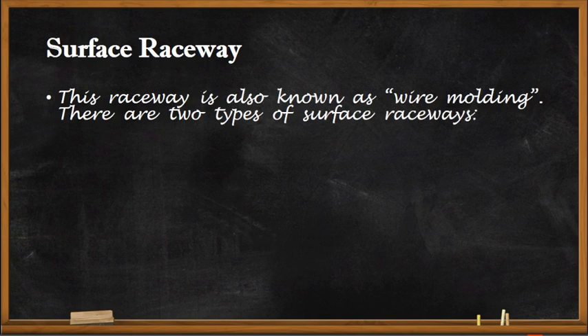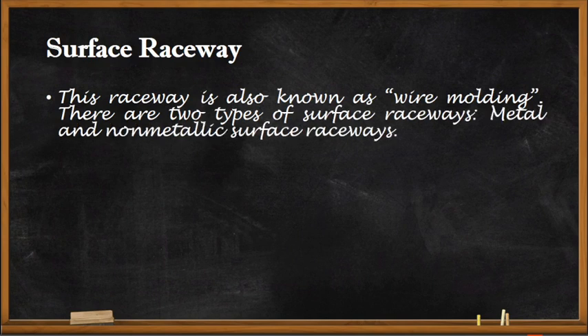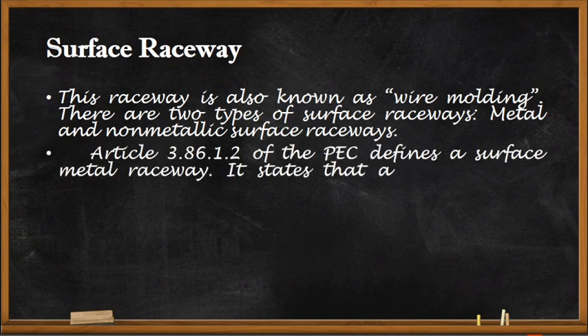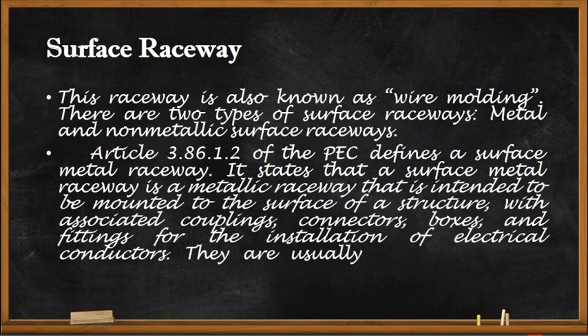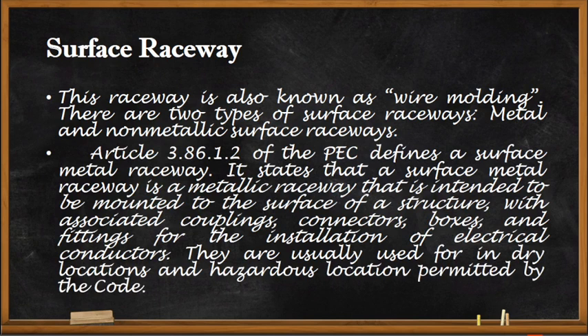Surface raceways are also known as wire molding. There are two types: metal and non-metallic surface raceways. Article 3.86.1.2 of the Philippine Electrical Code defines a surface metal raceway as a metallic raceway intended to be mounted to the surface of a structure, with associated couplings, connectors, boxes, and fittings for the installation of electrical conductors. They are usually used for dry locations and hazardous locations permitted by the code.